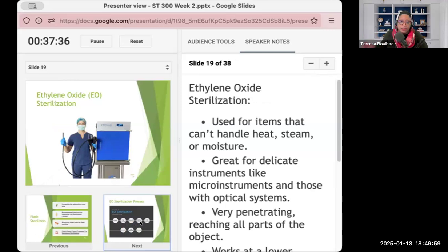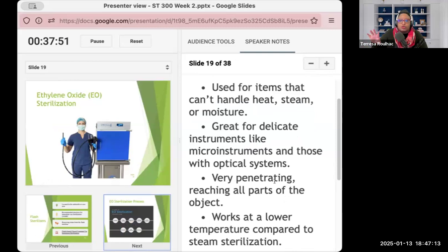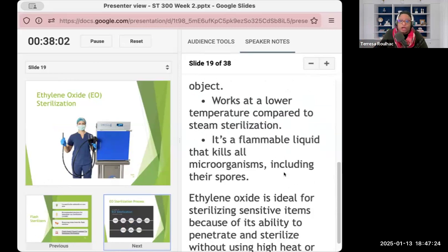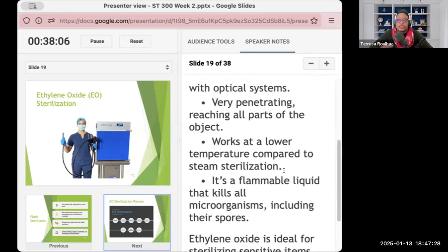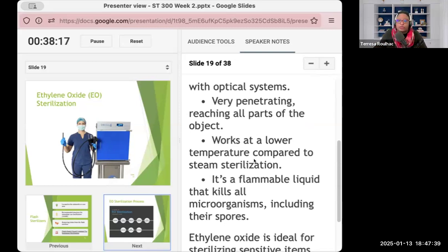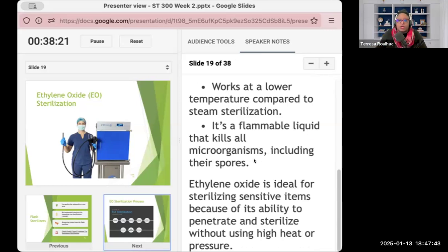Great answers. We also look at ethylene oxide, used for items that cannot handle heat, steam, or moisture. These are going to be able to penetrate, again, all parts of the object, just like the other autoclaves would. But remember, these are delicate. They cannot handle heat, steam, or moisture. So it works at a lower temperature compared to steam sterilization, but it is a flammable liquid. And that liquid does essentially the same thing. It kills all microorganisms, including their spores. So it's going to be ideal for sterilizing sensitive items because of its ability to penetrate and sterilize without that high pressure heat. Okay.